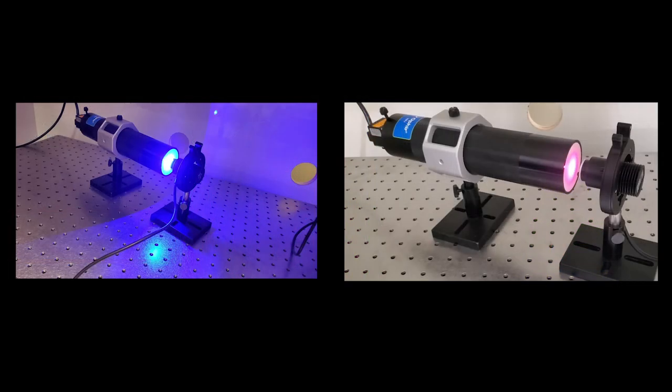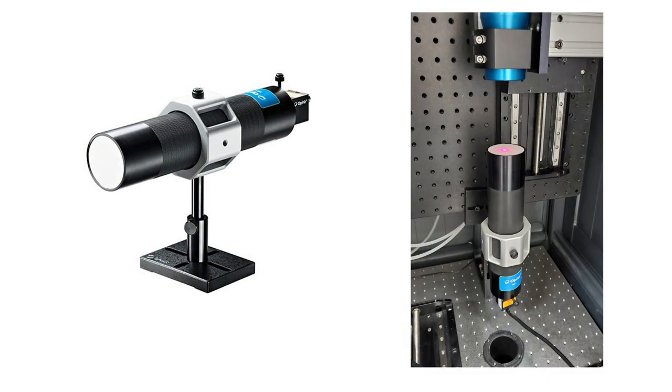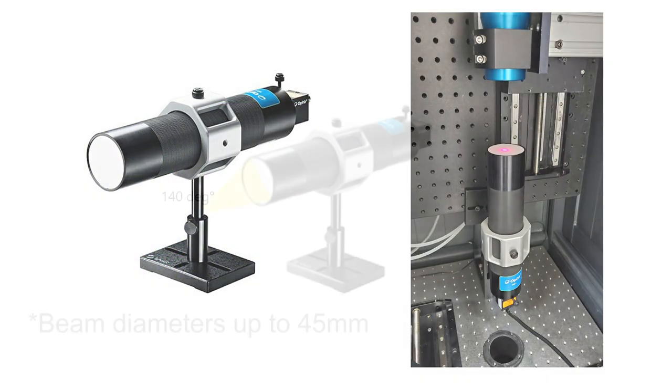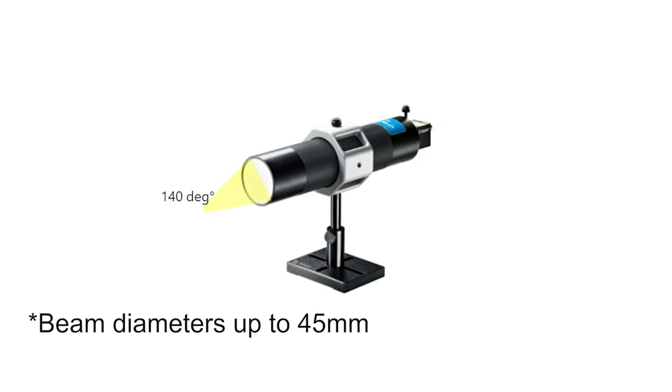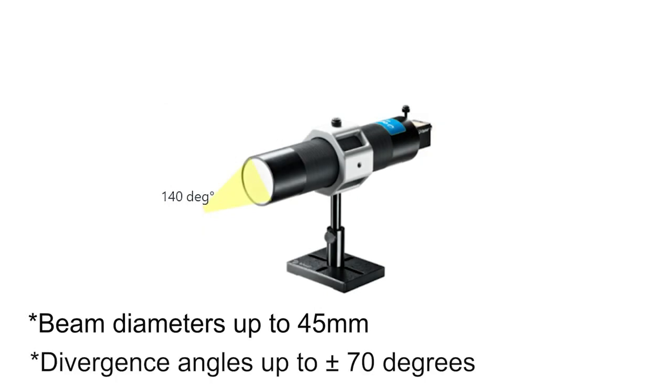The WBI operates over a wide range of wavelengths, from the UV, 350 nm, to the near IR, 1100 nm, for powers from hundreds of microwatts up to 1 kW CW. It can be used in a horizontal or vertical orientation, with beams having diameters up to 45mm, and divergence angles up to plus or minus 70 degrees. That's roughly 10 times the divergence angle that can be captured by a regular profiler camera alone.